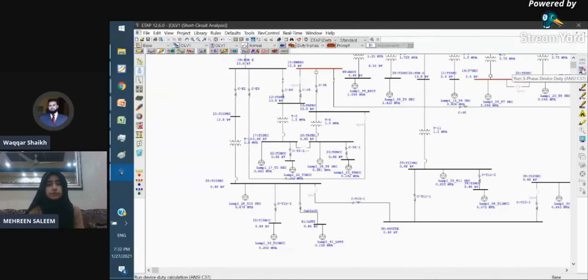One important thing to remember: it's not necessary that the symmetrical faults or three-phase faults are always of the highest value. Sometimes your asymmetrical faults are higher than the three-phase symmetrical faults, like when you have a transformer with a solidly grounded configuration, or a generator with a solidly grounded configuration. In such cases, line to ground faults will be of higher magnitude compared to three-phase symmetrical faults. So depending upon the scenario, you size your equipment, but three-phase symmetrical faults can be simulated from the first option here. If you want to see other types of faults, like double line to ground, you can use the third option, the run three-phase line to line option.